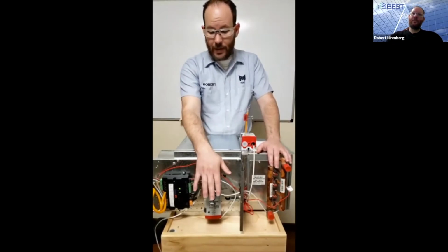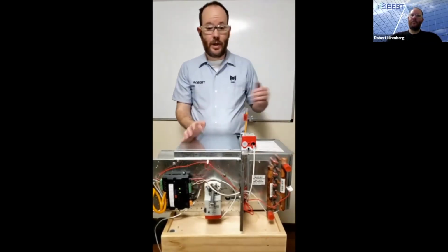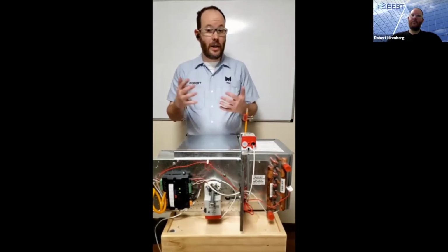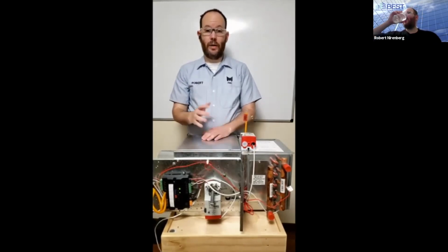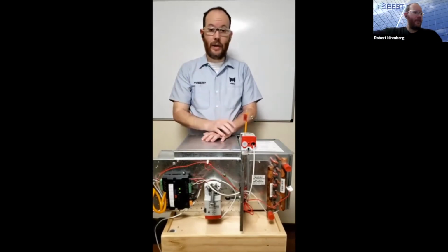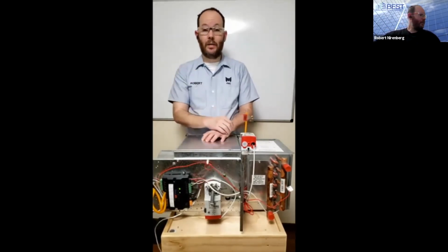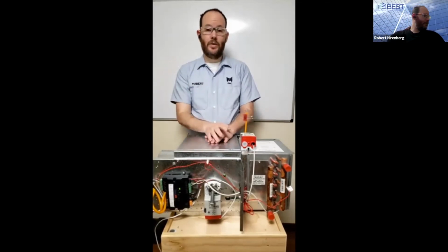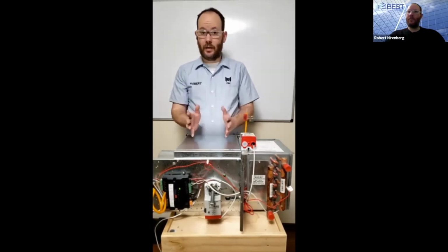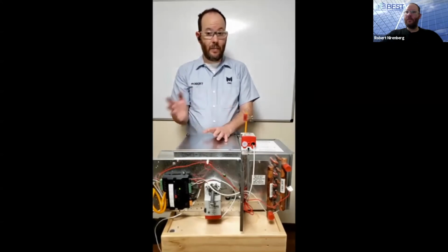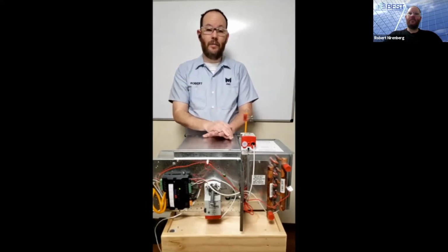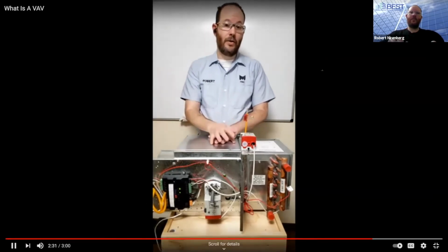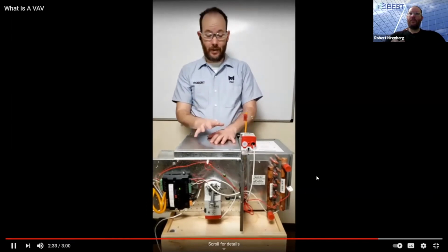The damper modulates to maintain airflow set points. There are typically two airflow set points, a maximum cooling set point and a minimum cooling set point. Maximum is intended for when the space needs more cooling because there are more people or there's a heavy heat load. Minimum cooling is a setting typically used when the space is satisfied or close to satisfied and doesn't need much heat or much cooling, to maintain it at a proper level while still providing enough fresh air to the space so that it doesn't feel stuffy.